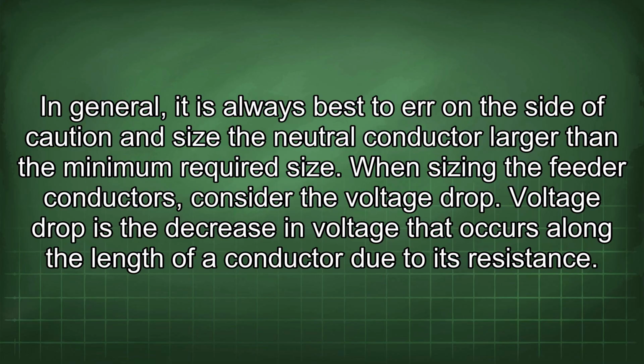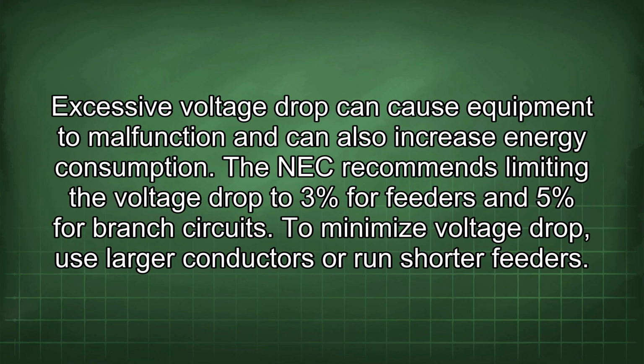When sizing the feeder conductors, consider the voltage drop. Voltage drop is the decrease in voltage that occurs along the length of a conductor due to its resistance. Excessive voltage drop can cause equipment to malfunction and can also increase energy consumption. The NEC recommends limiting the voltage drop to 3% for feeders and 5% for branch circuits. To minimize voltage drop, use larger conductors or run shorter feeders.